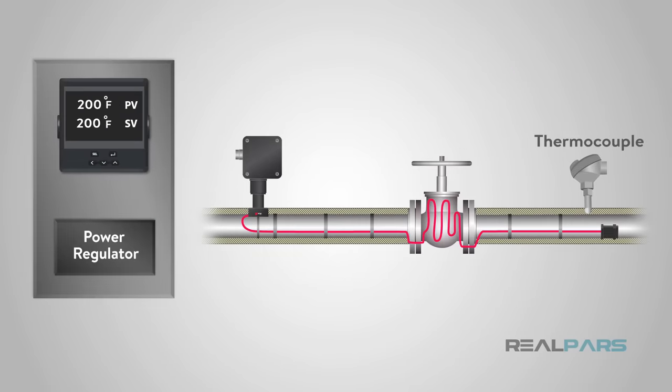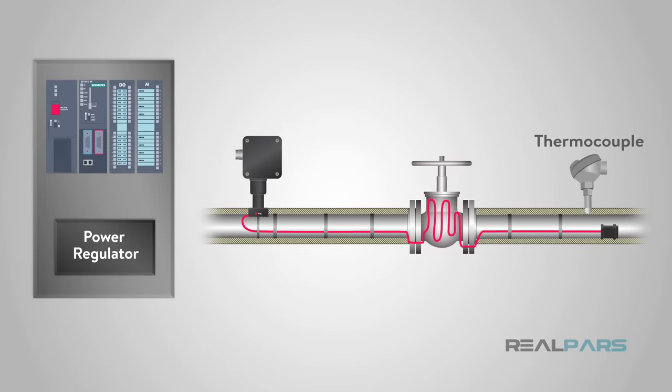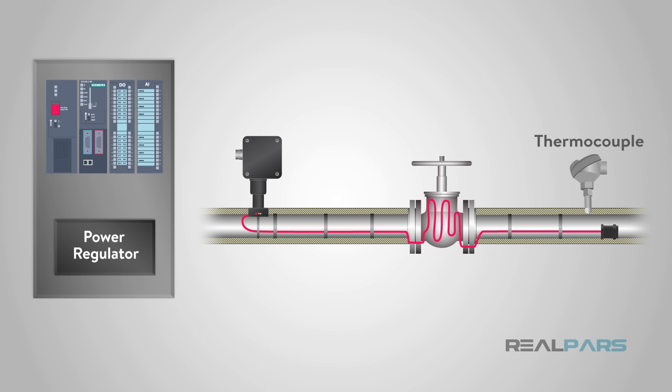We also have the option of setting up a PID controller with a PLC. Instead of the standalone unit, we can use the input and output cards already on our PLC. The process variable or control loop feedback would be wired to our input card and programmed into the PID.